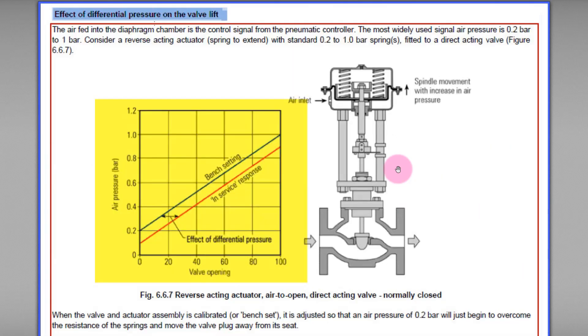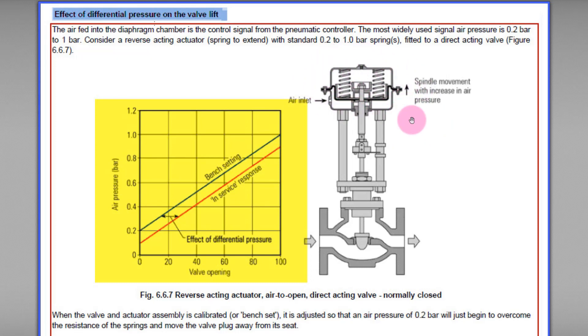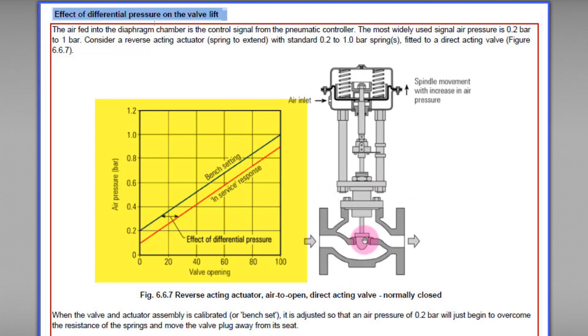Before we talk about the relationship between the valve opening and the air pressure curve, let's talk about direct acting and reverse acting actuators. This is a reverse acting actuator — we know this because the instrument air is applied to the bottom of the actuator. The valve body itself is a direct acting type.